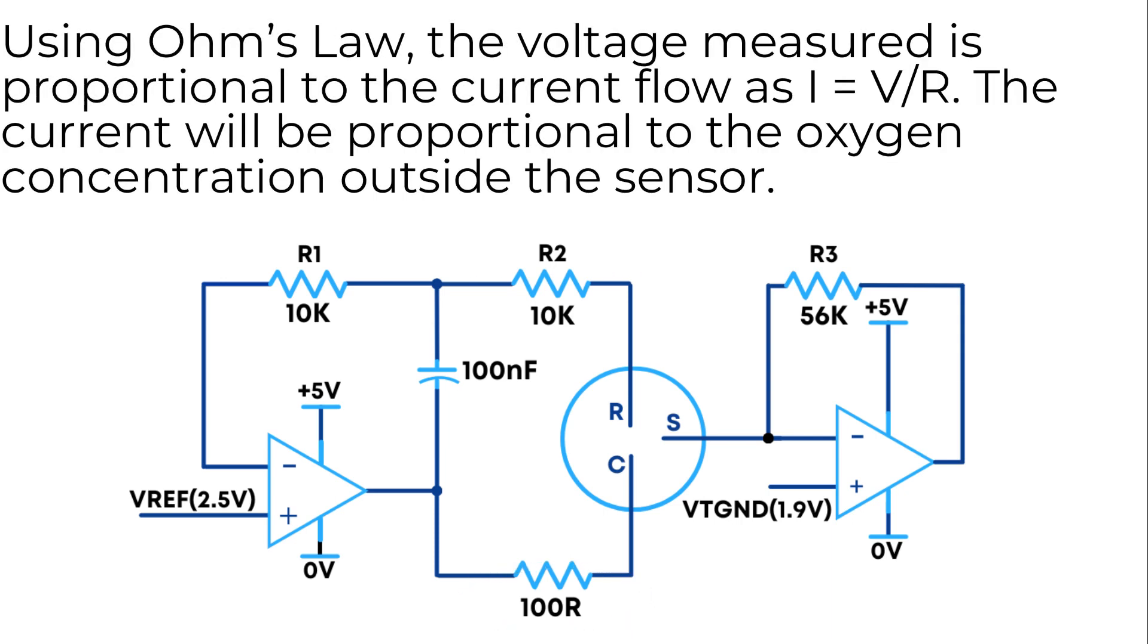Using Ohm's law, the voltage measured is proportional to the current flow as I equals V divided by R. The current measured will be proportional to the oxygen concentration outside the sensor.